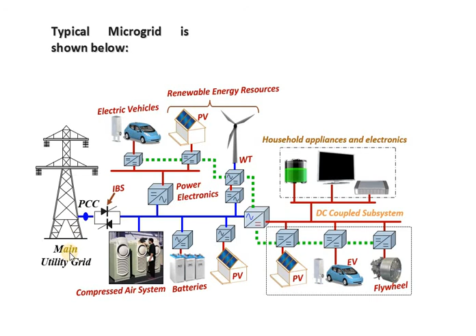Here we were discussing the PCC, the point of common coupling, used to connect the main utility grid and this particular microgrid. Then we will see what the need of a microgrid is. The first need: a microgrid could be an answer to our energy crisis, because it comprises distributed generation. The generation can take place with the help of local generating units. The second advantage is that transmission losses are highly reduced. Why? Because there are no long transmission lines. Since we are generating power for the local community, the lines transmit power over a very short distance, so losses are reduced.